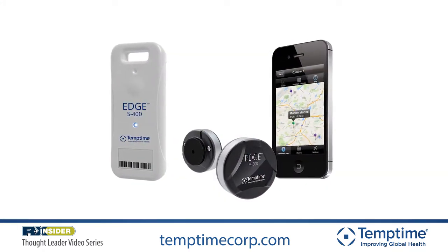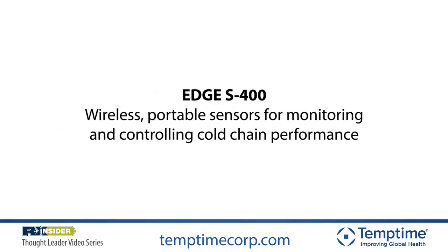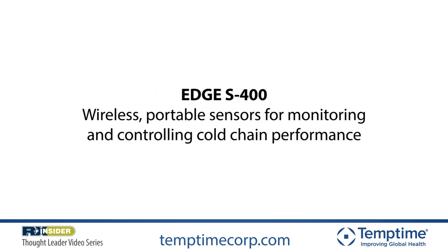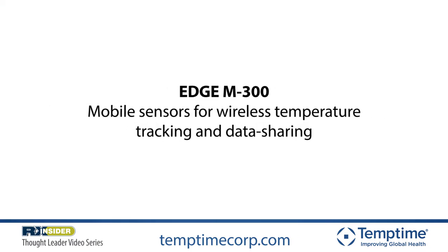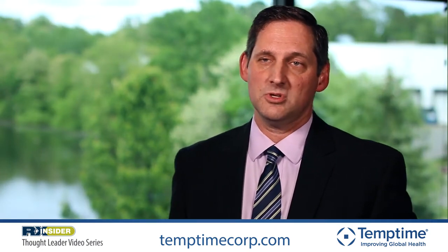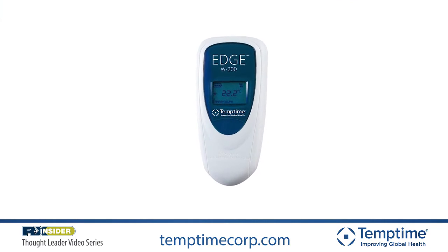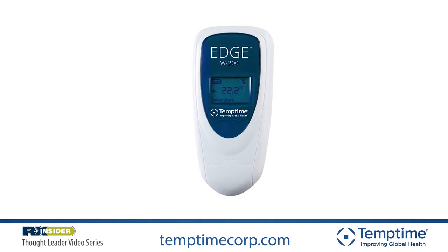We have three different products currently available. We have the S400 and the M300, both used primarily for transportation or shipping applications and also applicable for certain facility monitoring uses. The S400 is a disposable device — the battery lasts for three months and then can be disposed of. The M300 has a similar application but is reusable, and the battery lasts for one year and can then be replaced. The final device is the W200, which is specifically designed for monitoring facilities, whether for ambient temperature and humidity of a warehouse or for storage devices like a refrigerator or freezer.